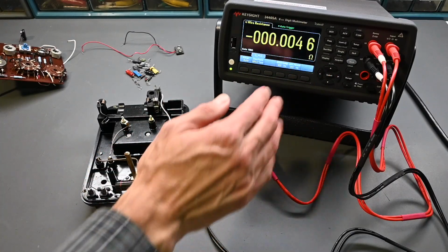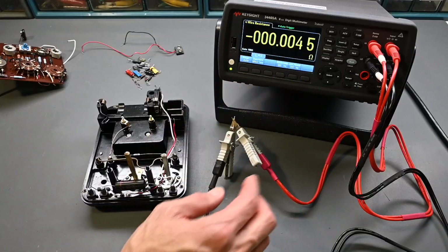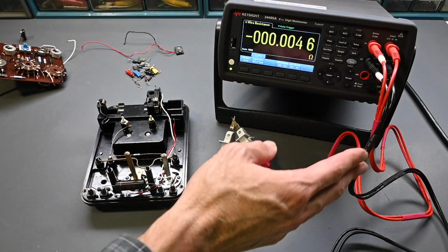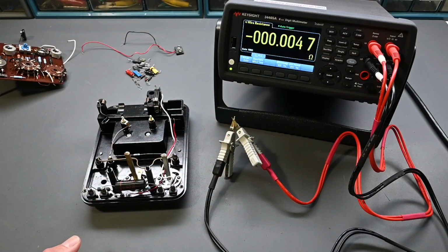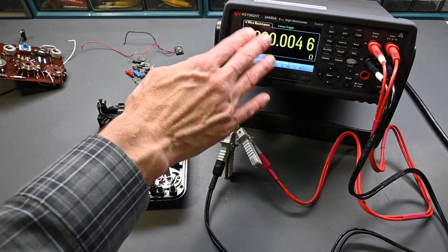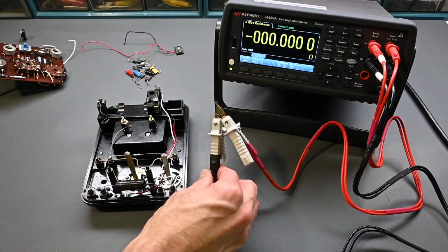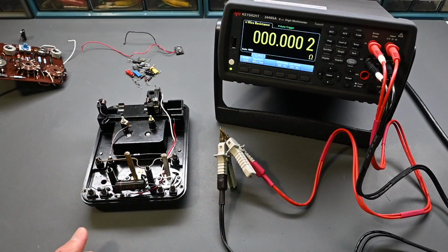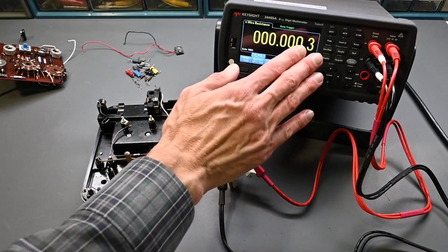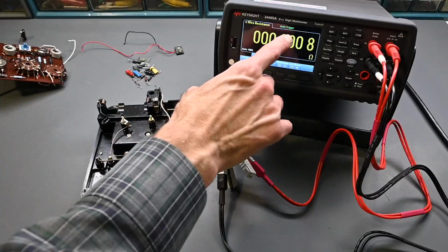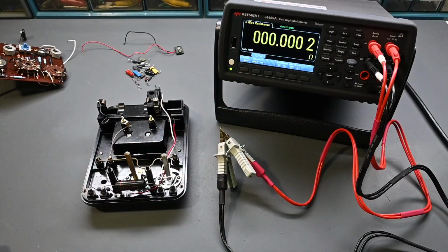And you can still null this out if you need to, but this is much closer to 0 than if we had the other way where you end up getting the lead resistance as well. So by using the 4-wire resistance mode and then these clips that are designed for the 4-wire measurement, you're able to get down to a very, very low value. You can see here, this is ohms and then milliohms and then hundreds of micro-ohms.